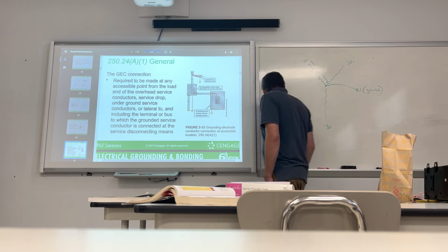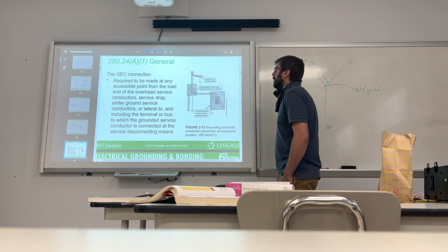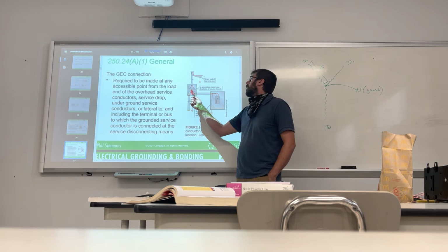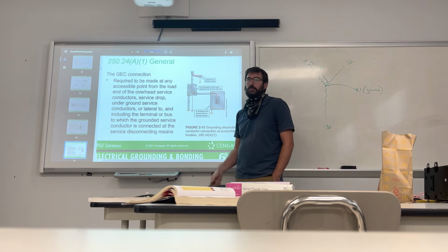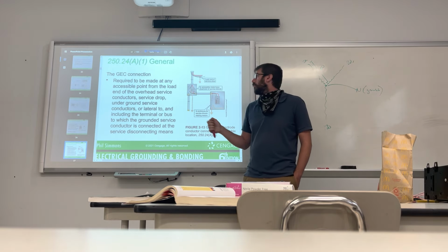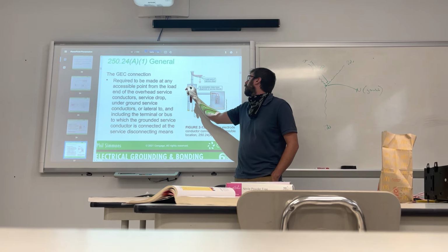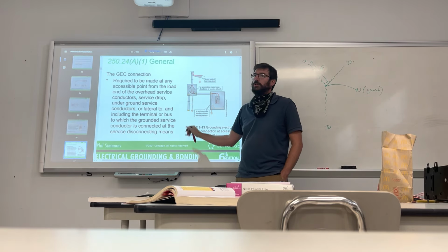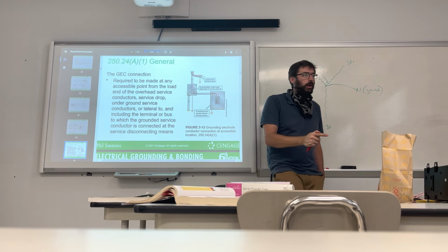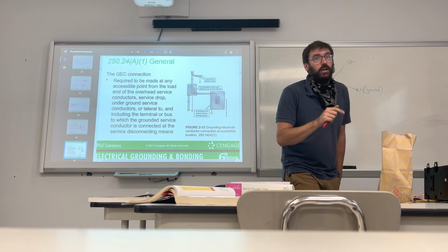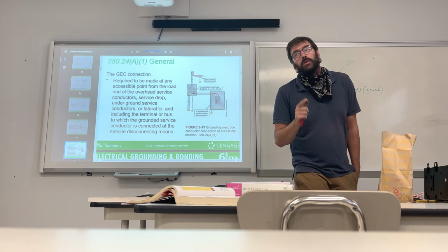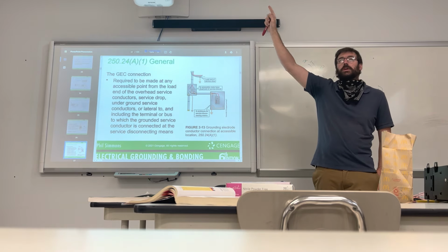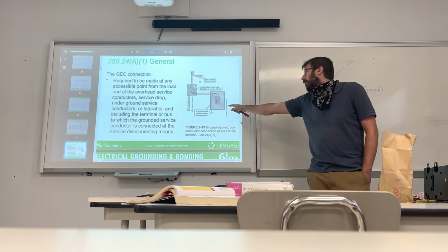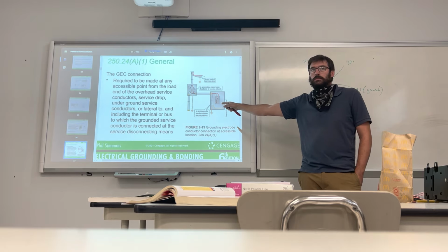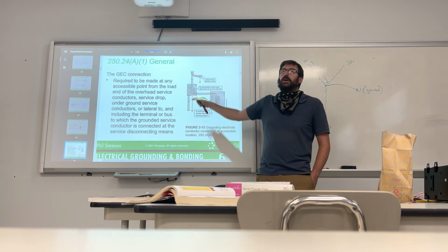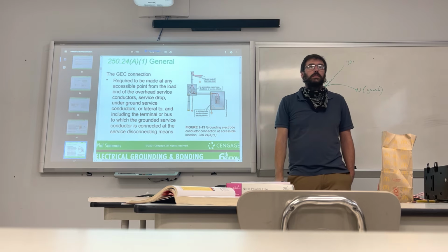Alright, so I have a little bit of insider knowledge on this. I know that that neutral connects right in the center, right underneath that meter base. And if you're going to ground that neutral, then there's a little lug off to the side of it that you can put a ground wire on in certain situations, and you can ground from that meter base too. But I never talked about the meter base, did I? I always said that it's grounded up at the pole off the transformer and in the main panel box. So why are they telling us that this might be an accessible spot for inspection?